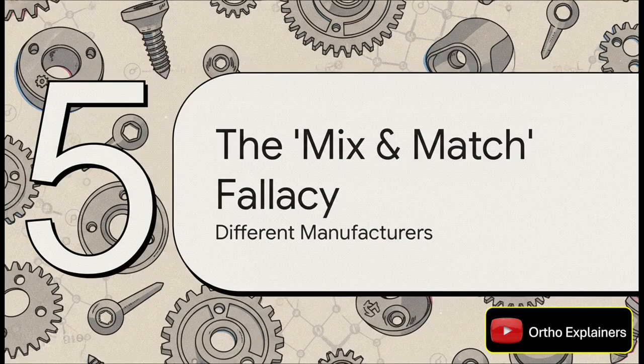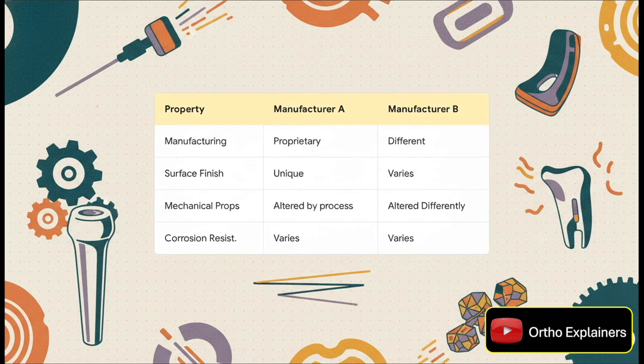This principle goes beyond just different metal types — it extends to mixing components from different manufacturers, even if they're specified as the same material, like 316L stainless steel. Same specification is not identical. Each manufacturer uses their own proprietary methods for milling, finishing, and heat treatment. These unique processes create subtle but significant differences in surface properties, microstructure, and ultimately corrosion resistance and mechanical strength.